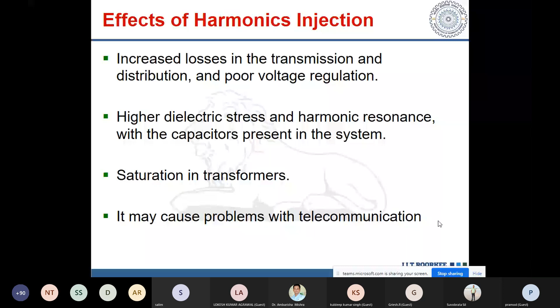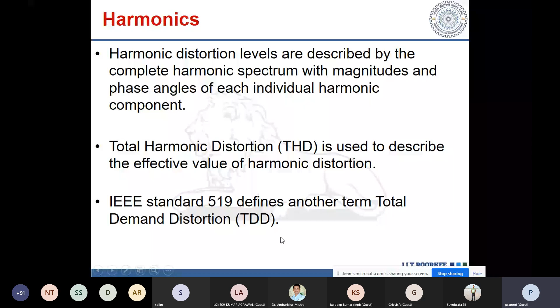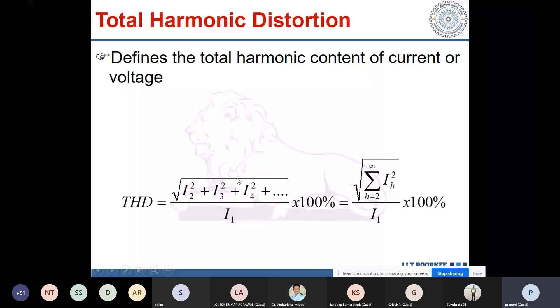We have seen that THD is used to describe the harmonic level, and THD is the RMS value of the harmonic current divided by the fundamental. That's how we define THD. Similar to the THD of the current, we can also define the THD of voltage, where the fundamental voltage is here and the voltage harmonics are here. It is the ratio of the RMS of the harmonic content to the RMS of the fundamental. All these are RMS values, remember.